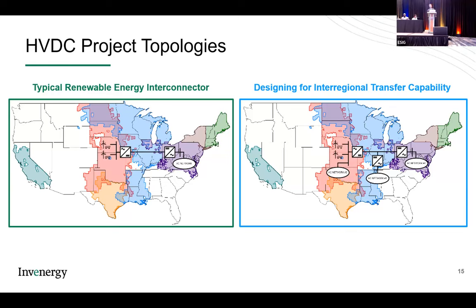So Grain Belt has really taken the shape on the right there, where it's starting to be built out as this interregional multi-terminal backbone, where you have a 5 gigawatt line providing transfer capability between SPP, MISO, and PJM, rather than just an islanded generation system in Kansas delivering to PJM. That's a one-purpose line. It's delivering power to a load and doesn't provide much more. Grain Belt is starting to be built out as what could be a key interregional backbone in the United States.